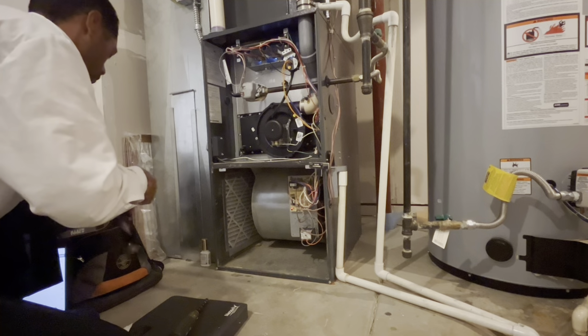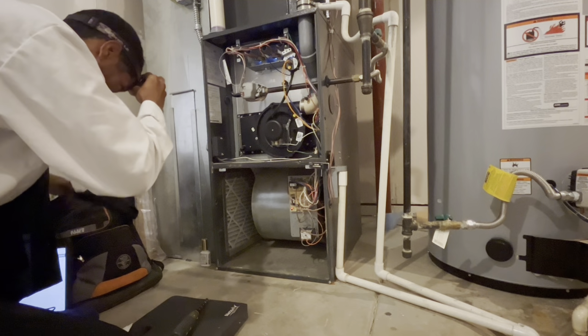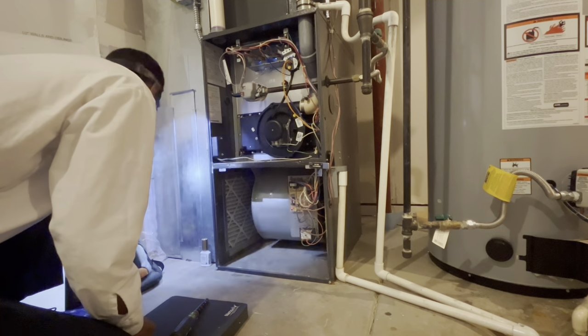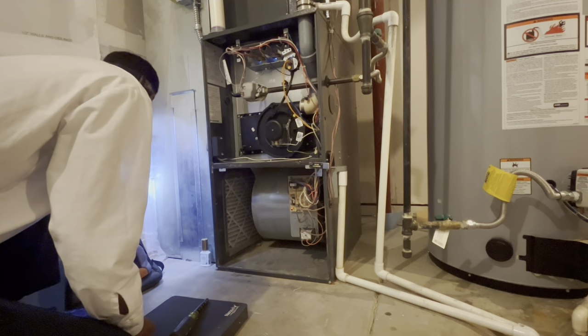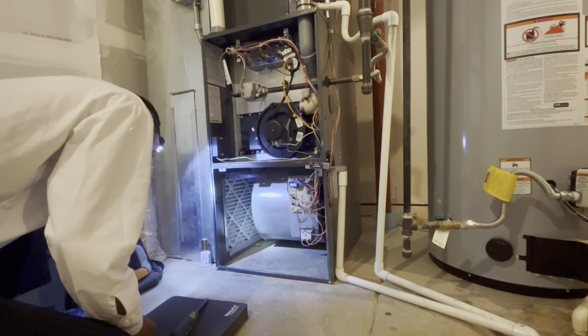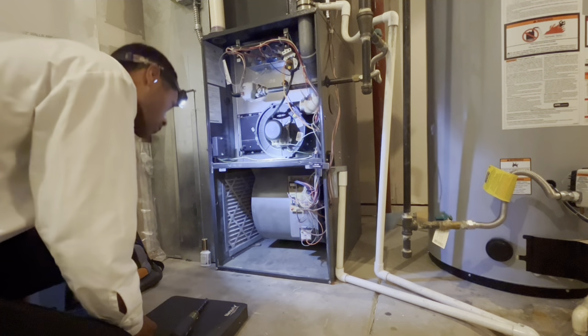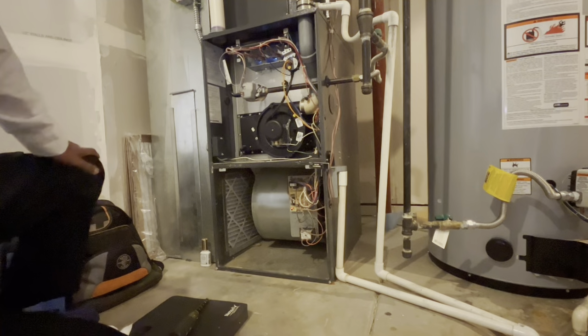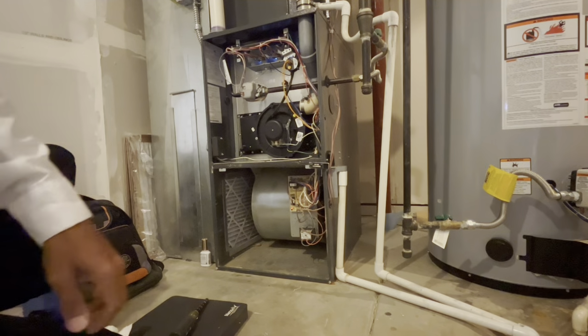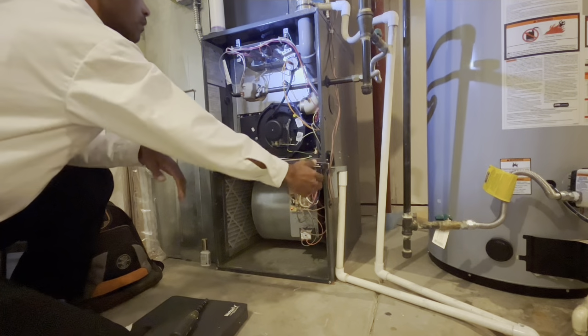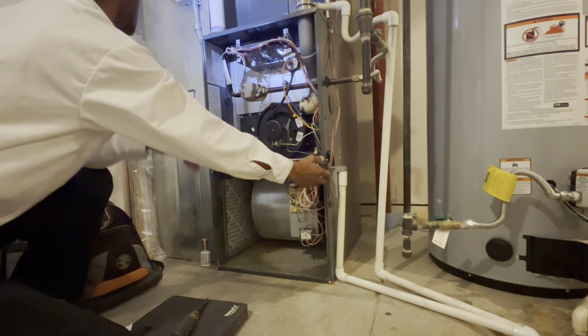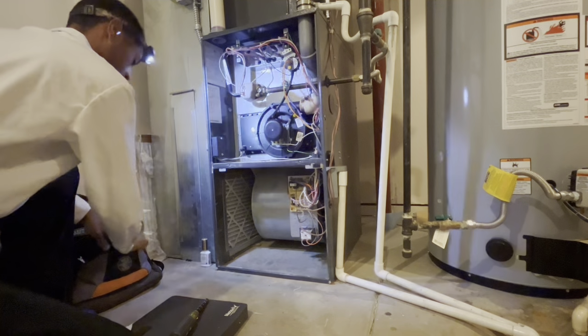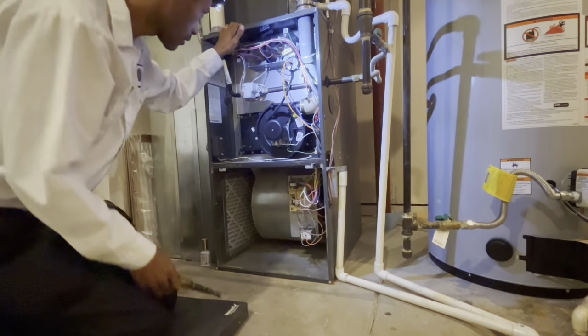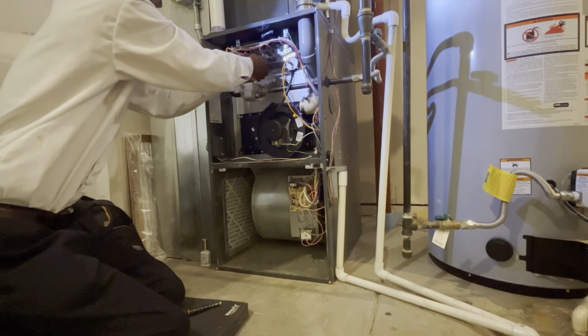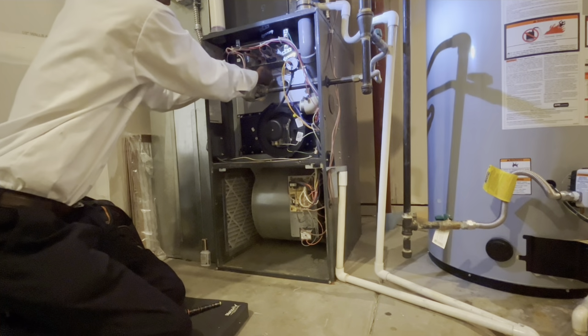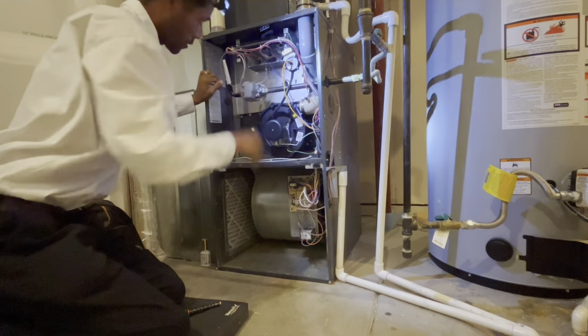So it's good. I'm gonna get my little headlamp on here. It's a very good thing to have when you're working on the furnace and basements and stuff like that. Sometimes you don't have a lot of light, so it's good to have some additional light to be able to work and see where all the screws are. So I'm like, okay, give them the thumbs up. It actually works. So now I'm going to take my magnetic holder off, and now I'm going to kill power at the disconnect going to the furnace, the 120 volt circuit. That way when I'm working on it, I don't bump that door switch and cut power on and blow a fuse or trip a breaker.